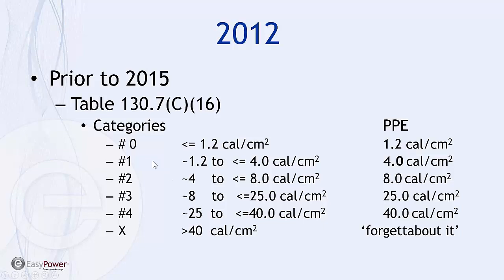If the incident energy fell into the range of 1.2 to 4.0, and you were within the arc flash boundary, you had to suit to Category 1, meaning PPE had to meet a minimum level of 4 calories per square centimeter. Likewise, for each succeeding range, if we calculated our incident energy to be between 8 and 25, we had to suit to 25, even though we were only a tad over 8.